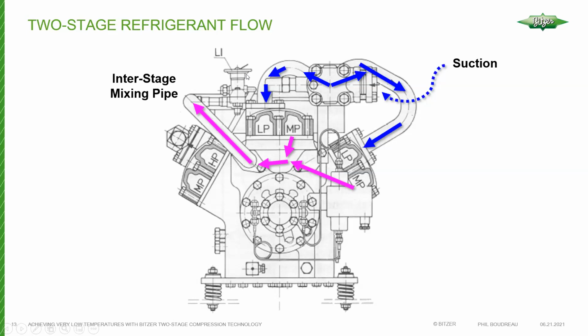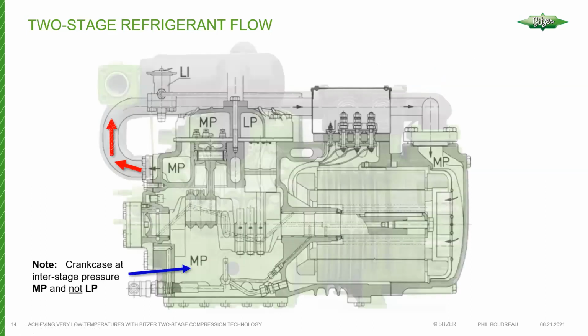And you'll see that there's a note there. It says LI. That's basically a liquid injection valve. This is a simple way of applying auxiliary cooling to this compressor, but I'm going to be showing you both methods. I just want to show you the flow path inside the compressor for now. Okay, so this is basically the low stage compression process.